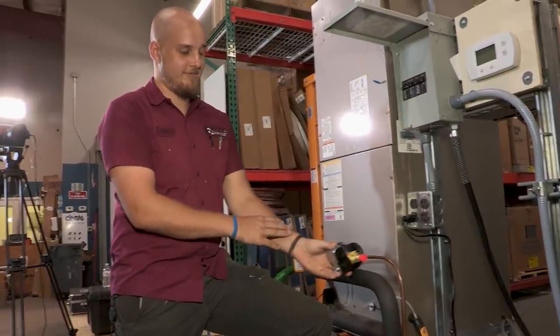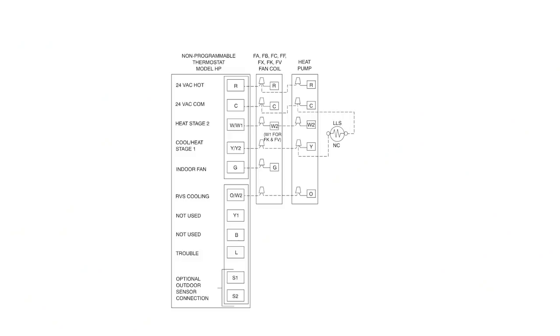that opens when energized, right? Because that's the configuration. And if you look at how the wiring diagram says it needs to be wired on the screen, take a look. How is it wired? One side goes to common, other side goes to Y, and see what it says down at the bottom of that valve? What does it say? Normally closed. So it's a normally closed valve, and you wire it in between C and Y.